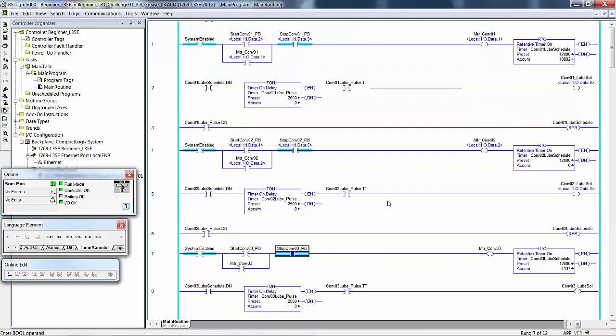Remember, we're headed for automation here. But whenever you are designing a control system, almost invariably, you will need a manual control system as well. In other words, in the manual mode, you will need to be able to start and stop the conveyors for testing, adjustment, maintenance, whatever. Now, you don't see any of that yet. We don't have auto mode, manual mode programmed in here. This is a simple 3 conveyor system, and we've already got 3 rungs per conveyor, so to speak.